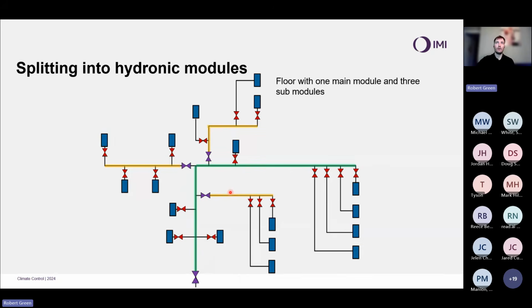And in this example, we have a floor with one main module and then 1, 2, 3 sub-modules running off there. And the idea with this is we then know we can set these 3 valves to here. So you can really see the idea of the partner valve. We can set up, okay, proportionally, let's set up here. And when I adjust this valve, the flow increases in this valve and this valve also. But then when I adjust this one, we know the flow that increases here is the same as an increase here. So therefore, I only need to measure this valve and measure what the increase happens as I restrict this. I can get these 3 valves proportionally balanced.